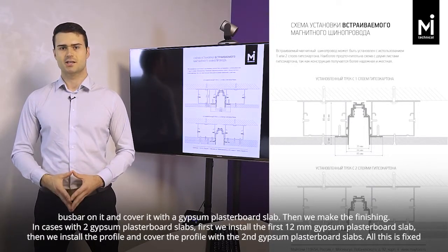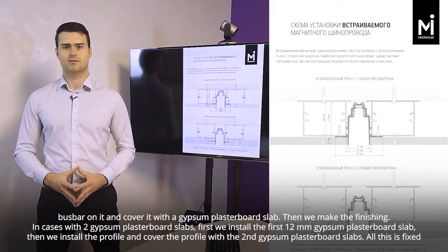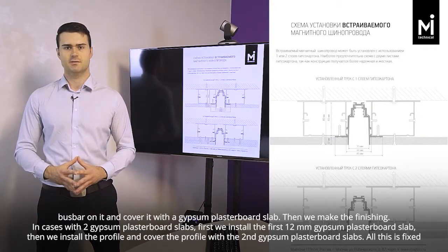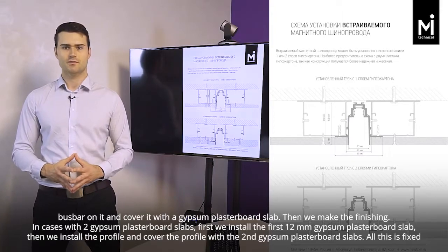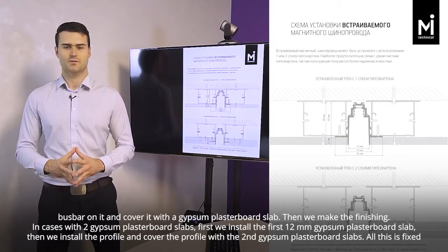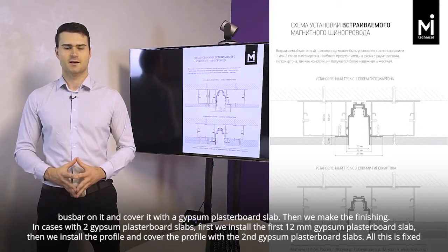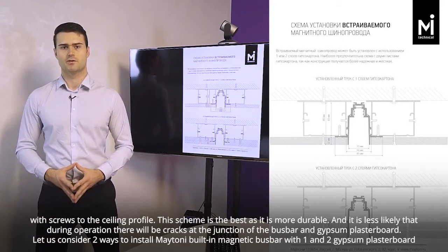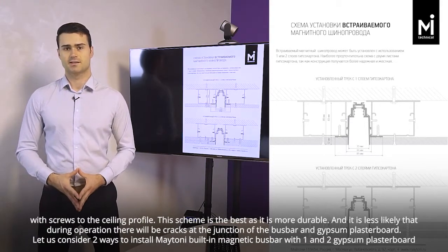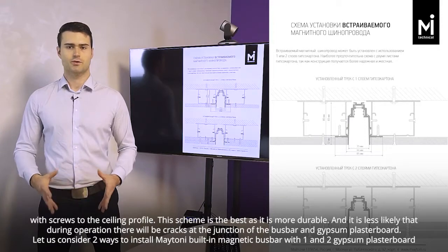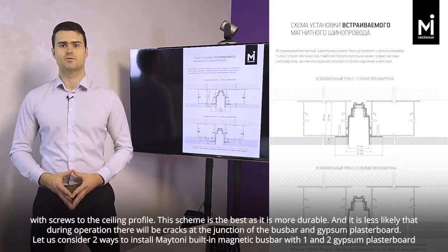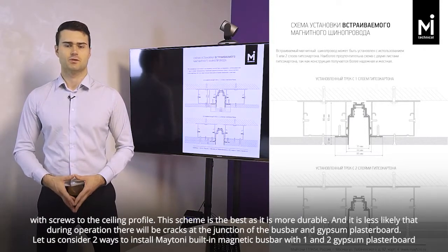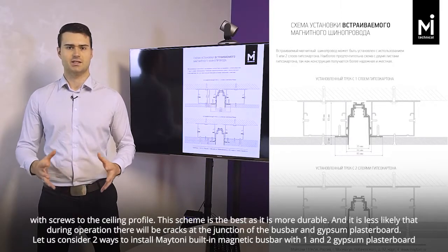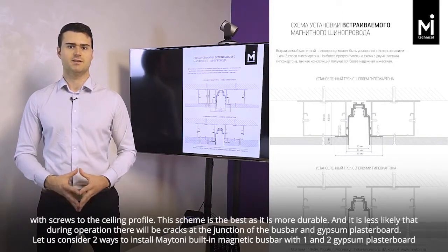In cases with 2 gypsum plasterboard slabs, first we install the first 12 mm gypsum plasterboard slab, then we install the profile, and cover the profile with the second gypsum plasterboard slab. All this is fixed with screws to the ceiling profile. This scheme is the best as it is more durable, and it is less likely that during operation there will be cracks at the junction of the busbar and gypsum plasterboard.